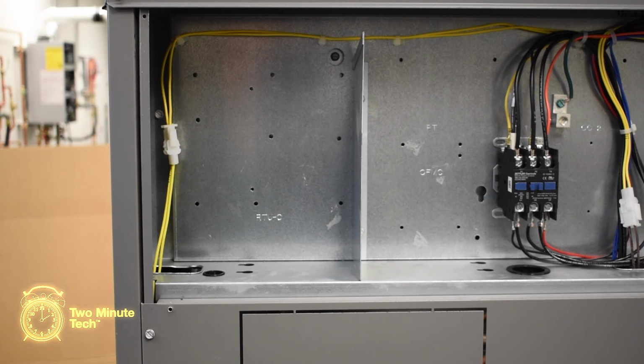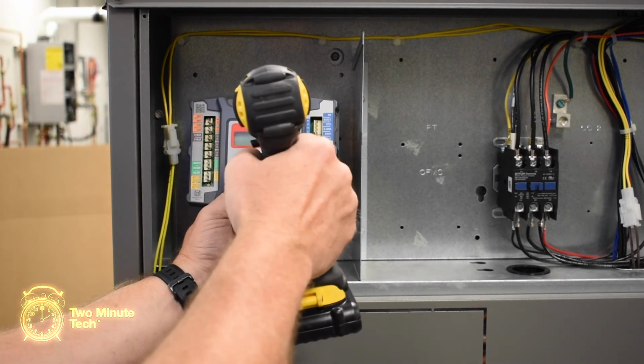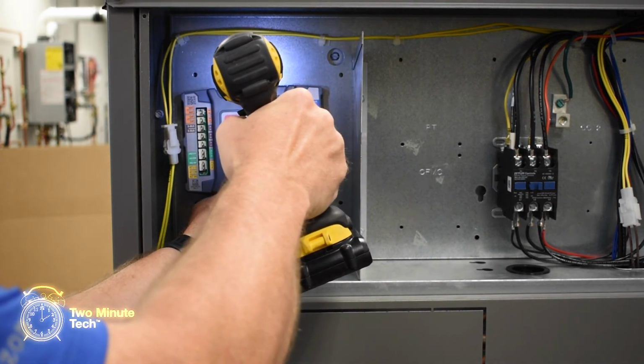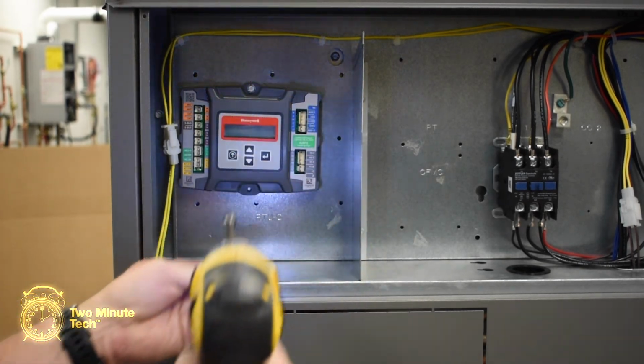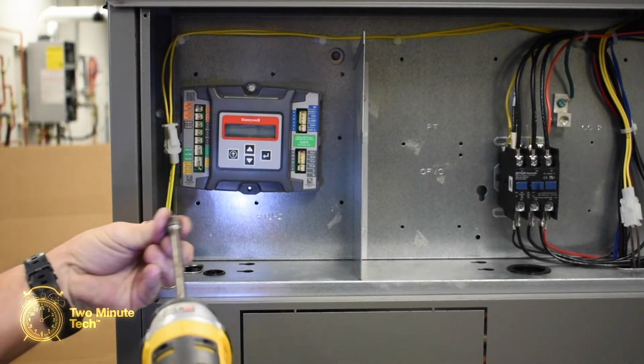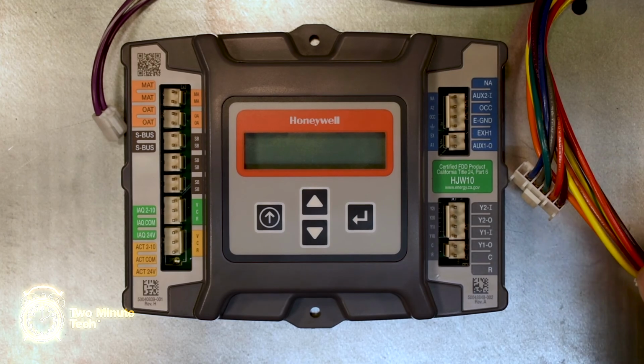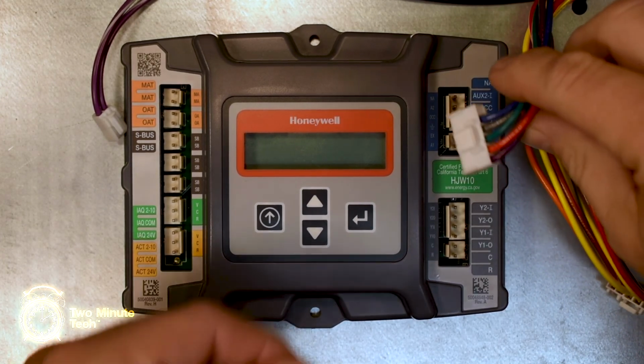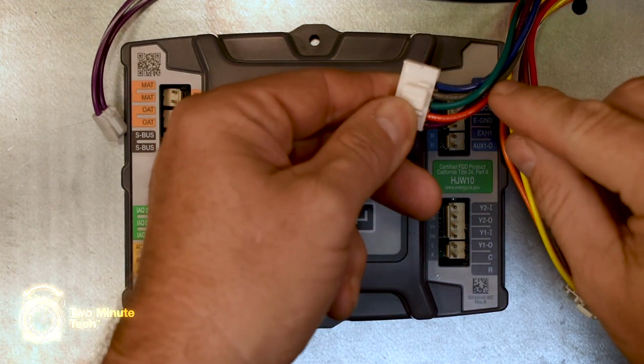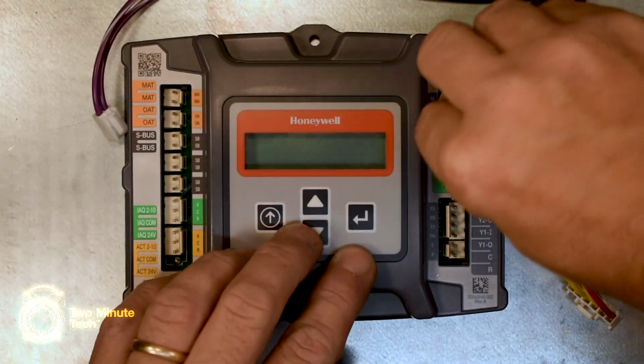The Honeywell Jade economizer controller will mount in the left-hand side of the control panel. Using the provided screws, attach the controller to the panel. Attach the wiring harness to the controller. The 6-pin plug with the blue, gray, green, red, and purple wires connects to the connector marked with blue on the upper left side of the control.